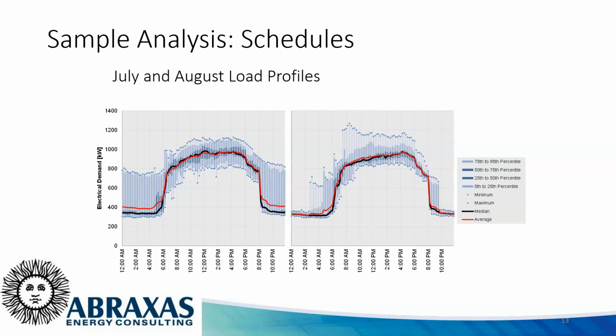But if you contrast the July profile on the left with the August on the right, you can see that overnight usage has dropped way off in August relative to July. An interesting thing here is that an easy way to estimate the potential savings, it's slightly conservative, is just by subtracting the median from the average for those hours when the lights or whatever it was were left on overnight. That's a simple way to estimate the potential savings if you can correct that operation.